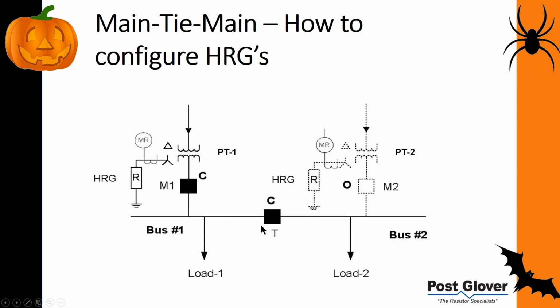Now, if you did have a closed transition, and for some reason got an immediate fault or whatever, you may have alarms from both sides of this thing—or if you chose to operate it from both sides, it's possible. But anyway, that's the way you want to do it. There's no real issue with paralleling these, even temporarily—that's not going to be a problem. You just need to expect that.